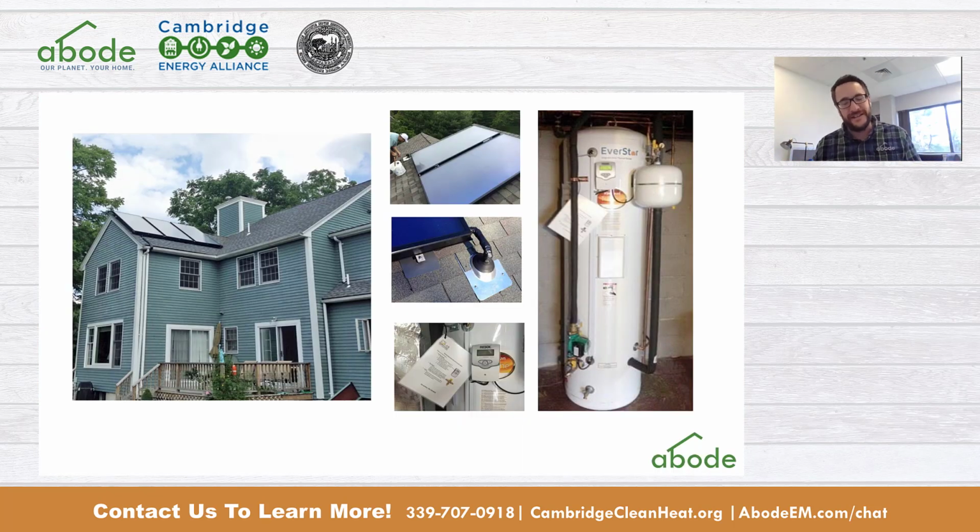The 2 options I'm talking about start with a traditional solar thermal system. In New England, the type of technology is called a drain back. At night, when the sun's not shining, there's no fluid inside of the panels or in any of the exterior piping, so there's no chance of any pipes freezing or bursting all year long. The components are the solar collectors up on the roof, taking the radiation from the sun, transferring it into the panels, and then transferring that liquid into the storage tank, which is going to be heating up the hot water all spring, all summer, up past likely 120 degrees, and it's going to meet pretty much 100% of the load those 3 months of the year.